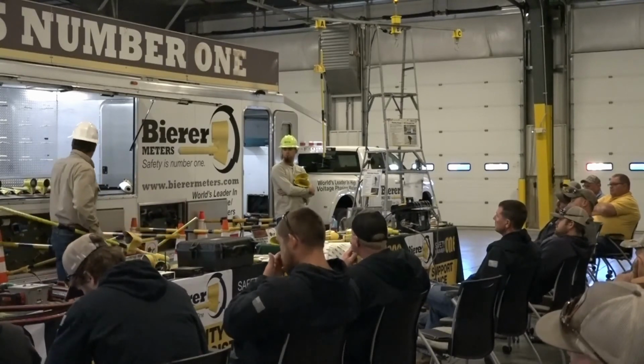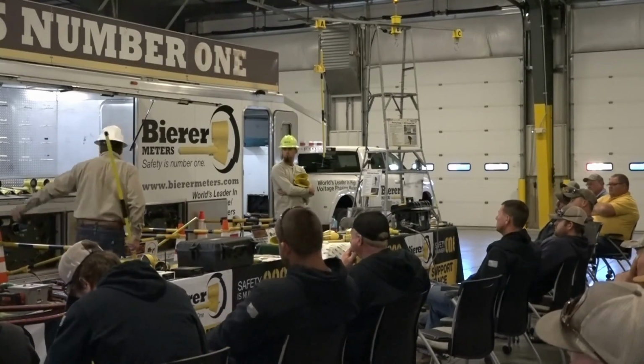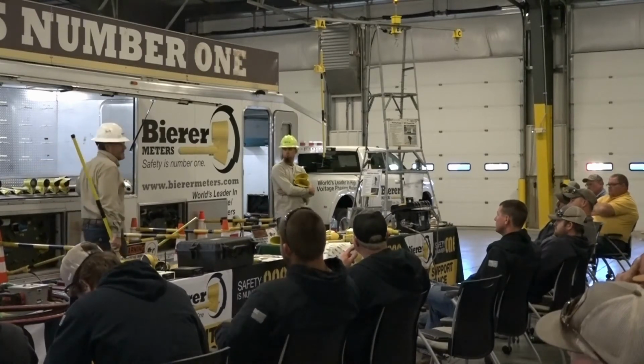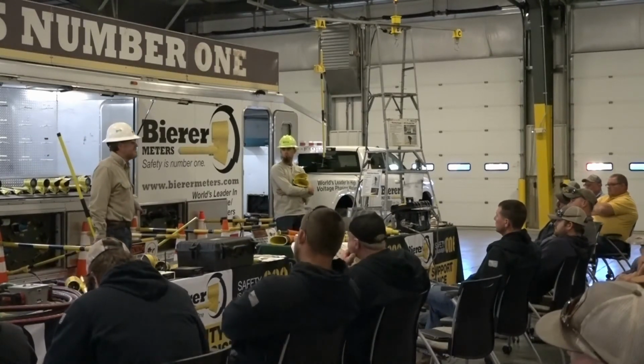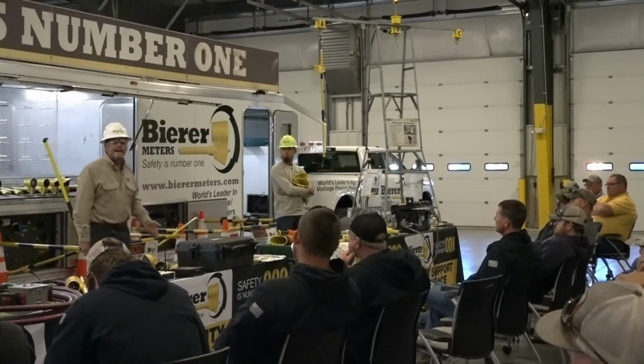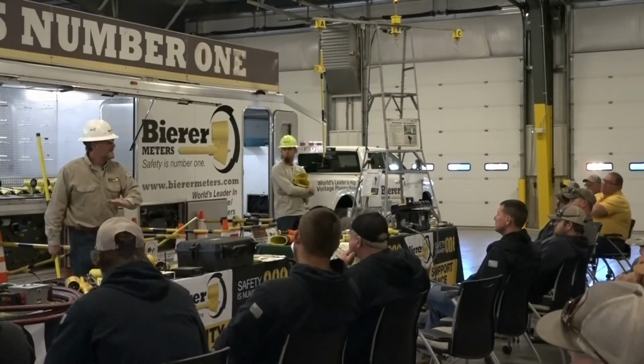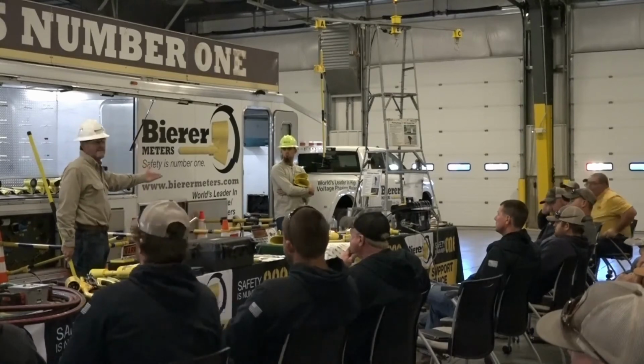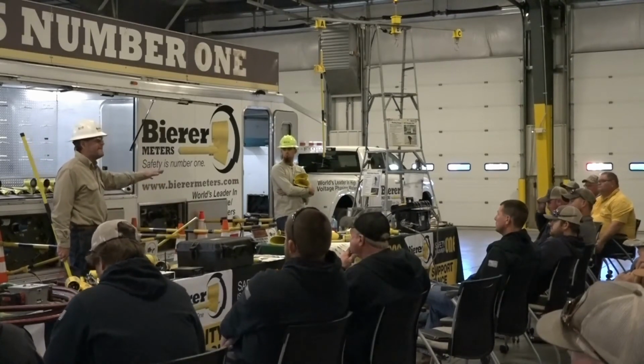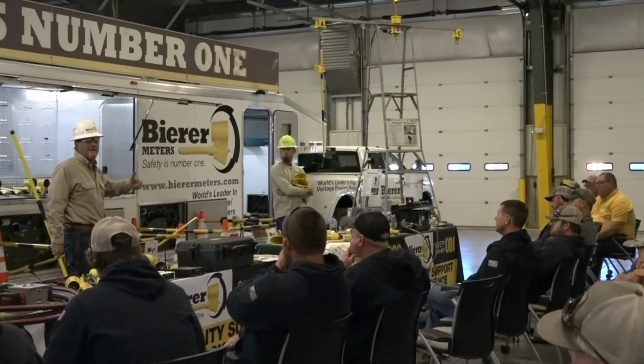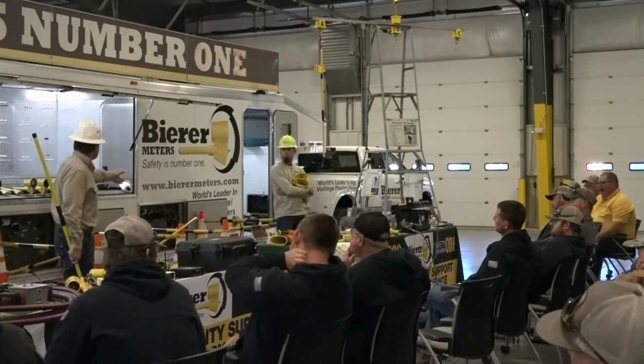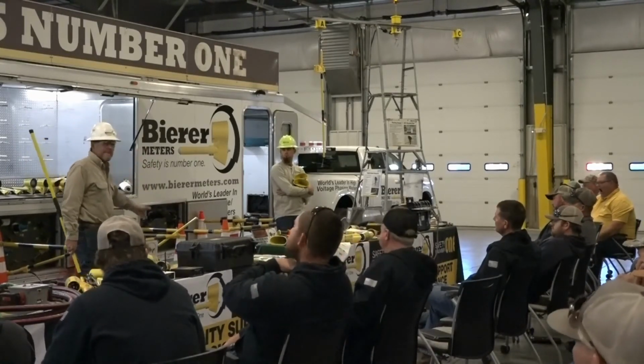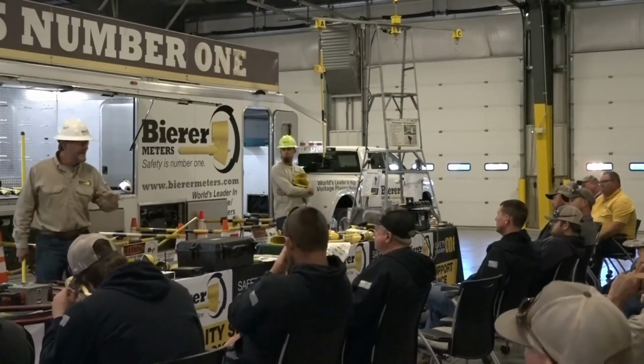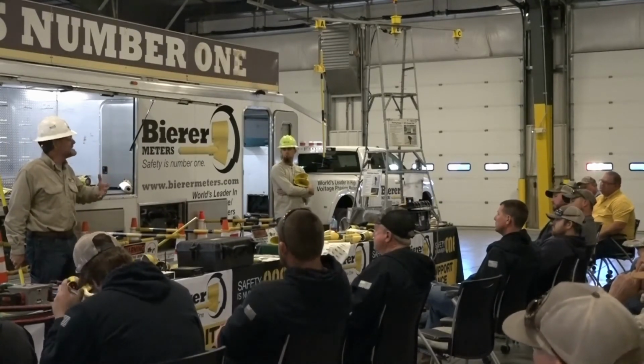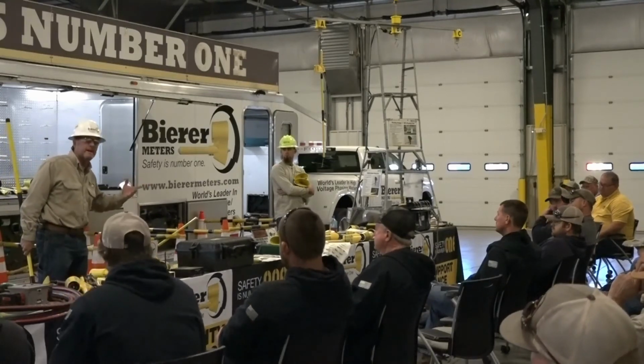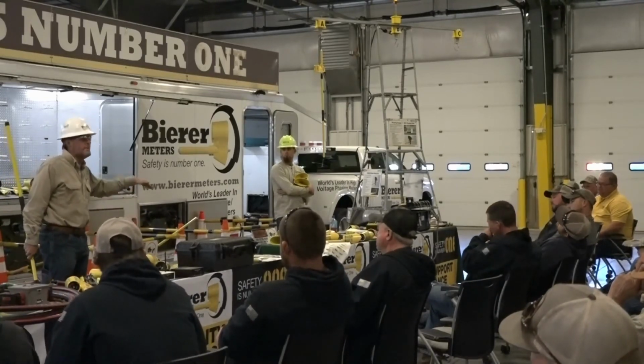Now, if he makes contact with this hot bushing, so 300 volts here, 20,000 volts here, and he makes contact with that hot bushing and gets a blue light at about 120 degrees, he knows that's the next phase out of sequence from A, that's a B phase. He knows A, B, C. If Dylan touches the capacitive test points over there and gets a red light, seeing close to 240, he knows that's the second phase out of sequence from A. He knows it's a C phase, 240 degrees.